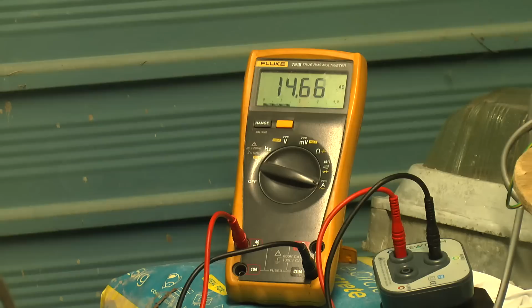Leakage current with the UPS off is about 14-15 milliamps, and with it on, we can see now why the RCD was so grouchy about it - it's right on the limit.